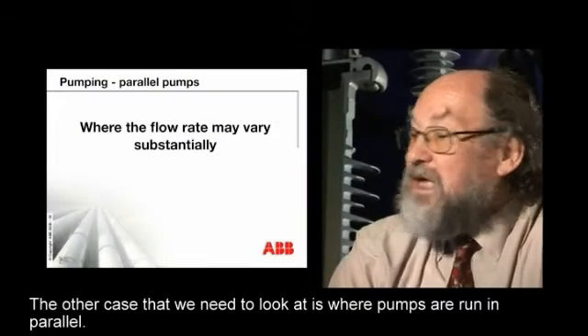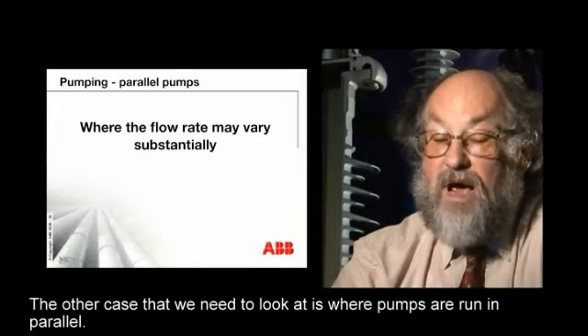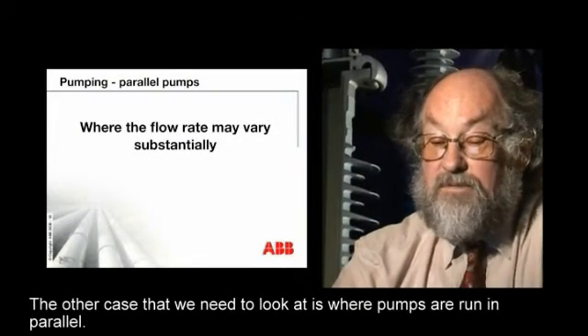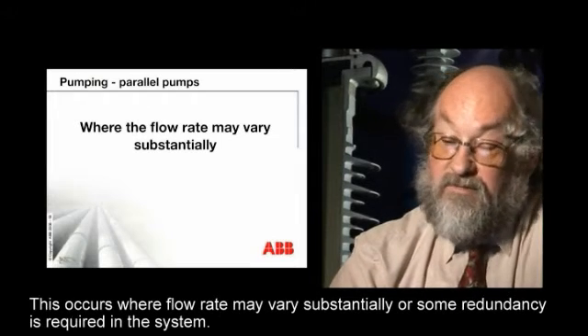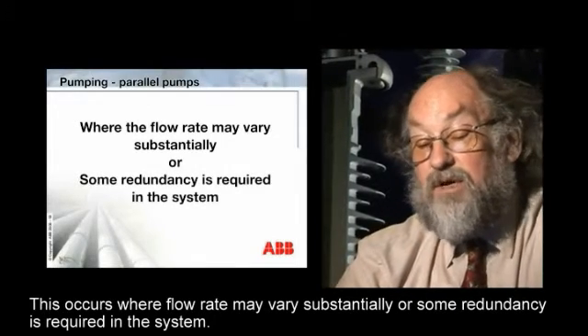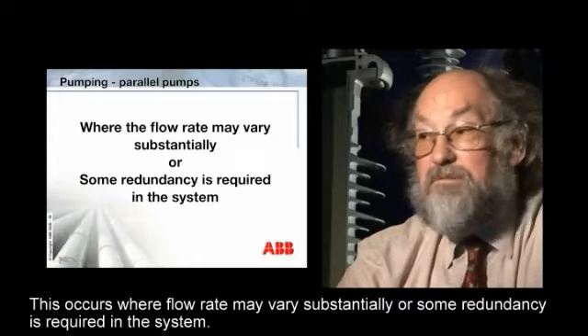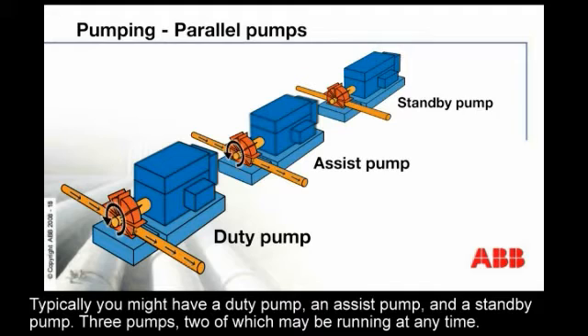The other case we need to look at is where pumps are running in parallel. This occurs where flow rate may vary substantially or some redundancy is required in the system. Typically you might have a duty pump, an assist pump, and a standby pump — three pumps, two of which may be running at any time.